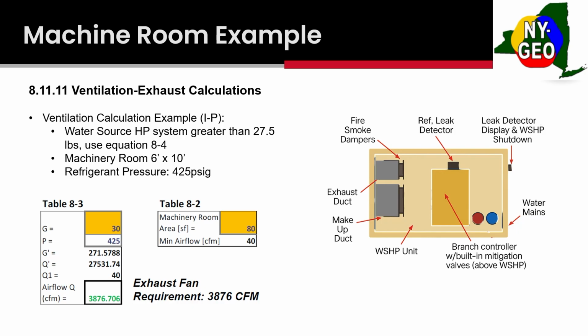But we're going to take our machine room, our minimum airflow per Table 8.2, and plug in our formula here. We've got our refrigerant and our refrigerant pressure in P, and we plug all that in. And for that one little heat pump, we need over 3,800 CFM of ventilation. This seems to be the biggest challenge with machine rooms with the A2Ls. And this is a tiny room, 6 by 10. We usually have more room, but in this small space, we need a lot of ventilation. So imagine having to add exhaust and makeup air to this kind of space.